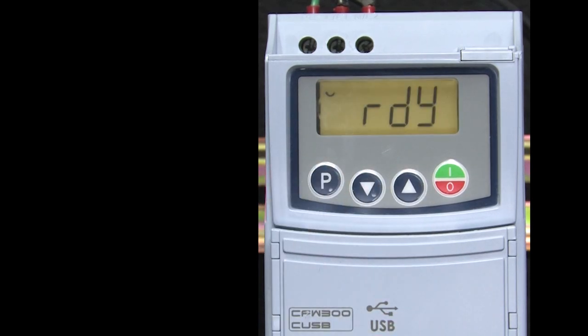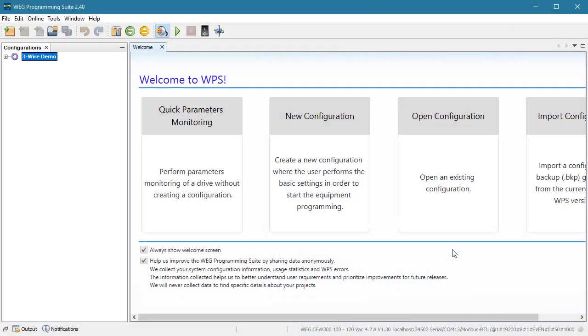Now you can do the entire setup from the HMI on the drive, especially since we are only going to modify three parameters. But I'm going to use the WPS software for this demo because it's easier for you to see what I'm doing. Just know that you don't have to use the WPS software and the extra accessories it requires.